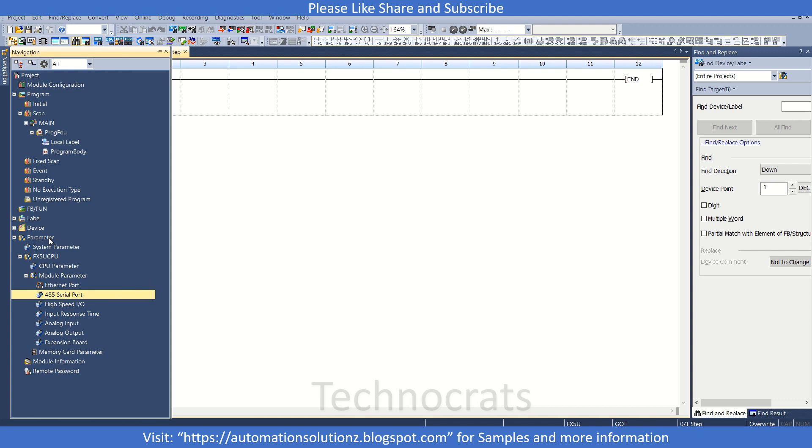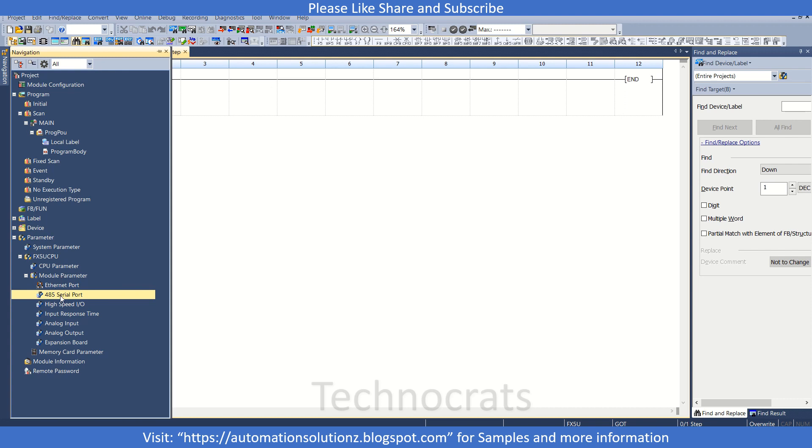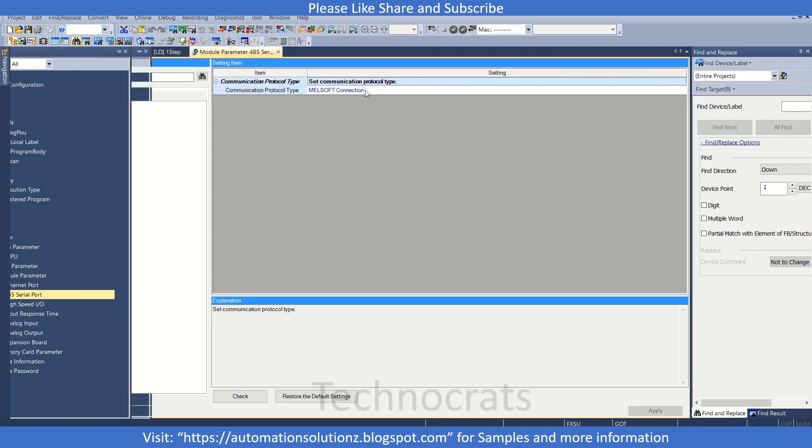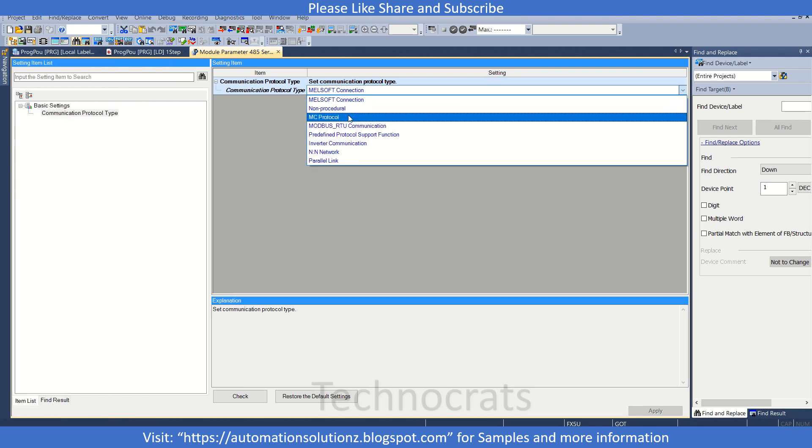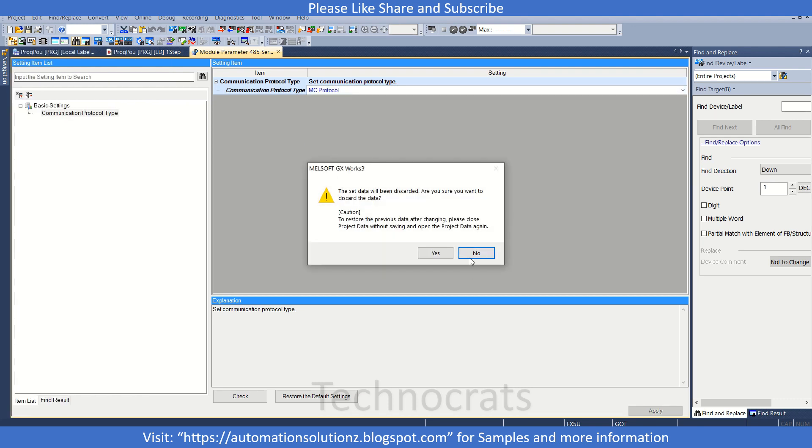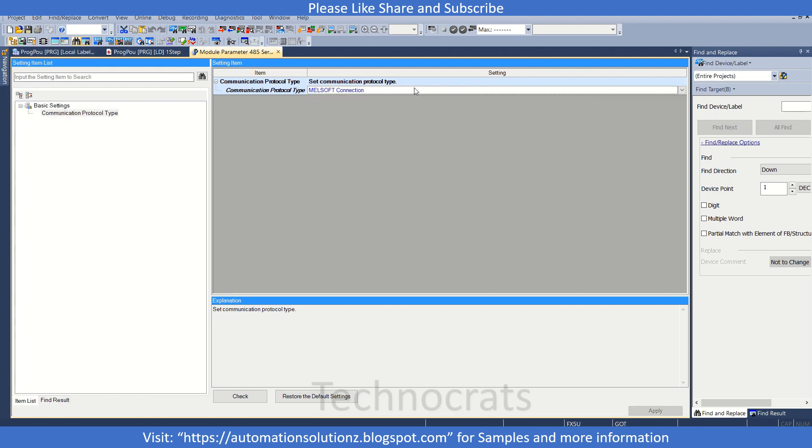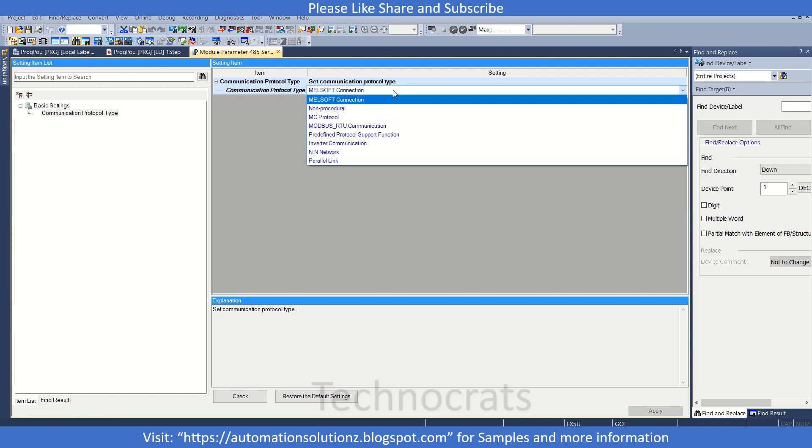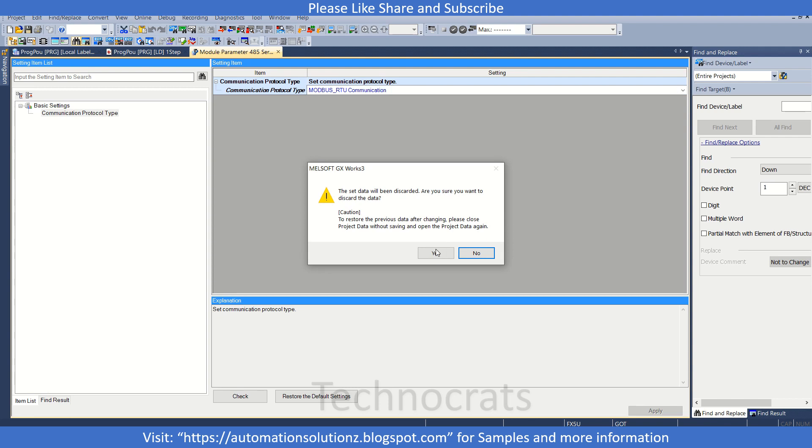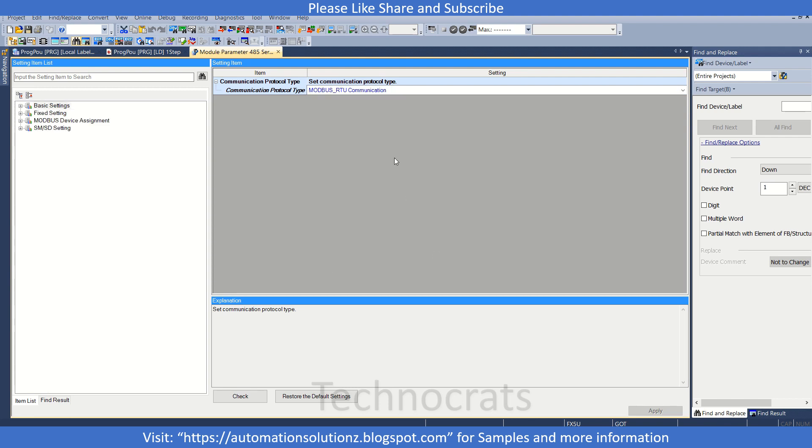That is 485 serial port setting. Here in module parameters, now I will select Modbus RTU communication. This is the setting, so do the parity bit, stop bit, and baud rate according to the requirement and click apply. I will use even parity. I will apply, check, and close this window.